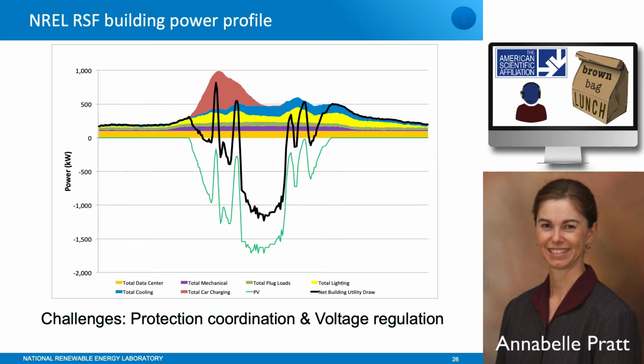So this reverse power flow has some challenges. The two main ones are protection and voltage regulation. Those devices, when we talked about the self-healing system, your local protection that acts - those devices were designed, their settings were set up expecting power to flow in a certain direction. So much work and thought is going into how do we adjust our protection settings and design new protection devices that are better able to deal with bidirectional power flow.